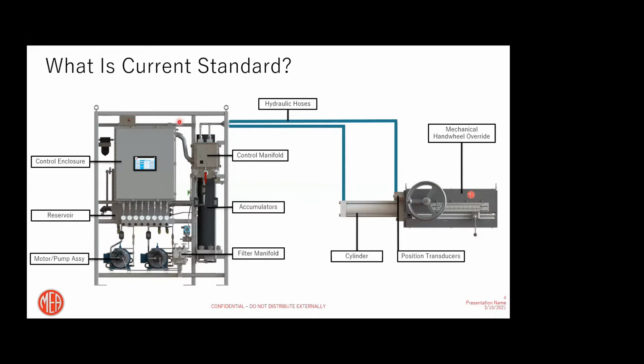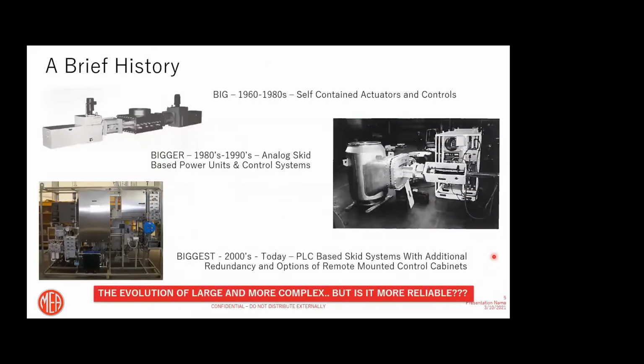All of this is controlled by some type of PLC-based controller. We monitor the position of the valve and then compare it to the signal, positioning the actuator to the proper location. So there are quite a lot of things in these quite complex units. And basically, how did we get to this point?